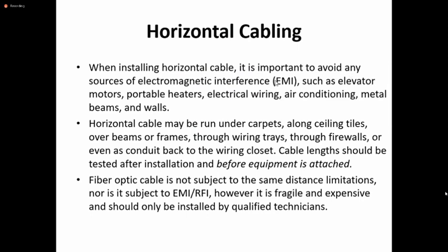Right. So you have to avoid any EMI, such as motors or heaters, wiring, air conditioning, metal beams, and walls. So it can be put under carpets or in the ceiling, over beams, wiring trays, through firewalls. Even as conduit back to the wiring closet. So you can put it inside conduit pipes also, right?